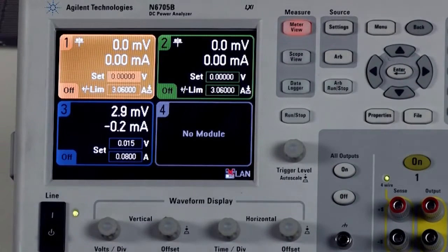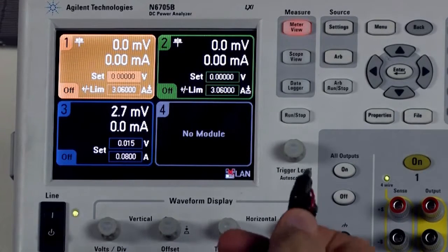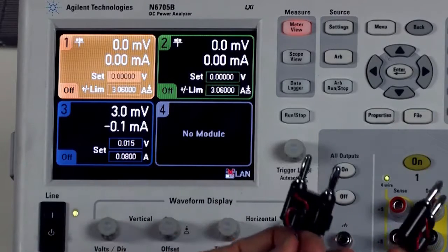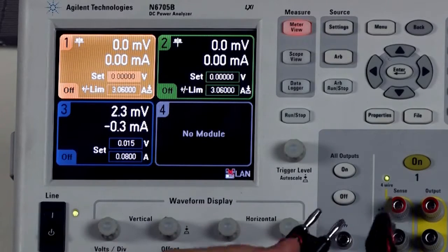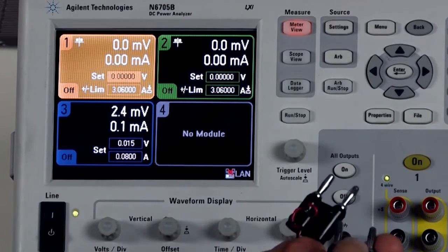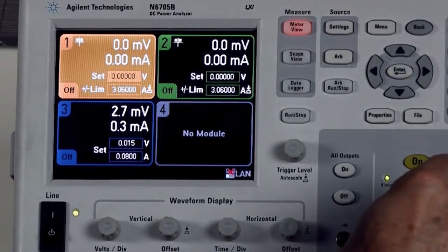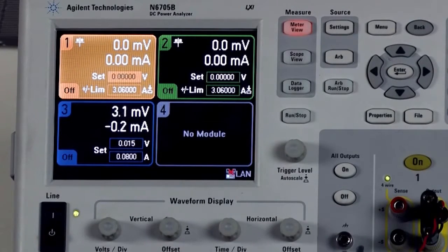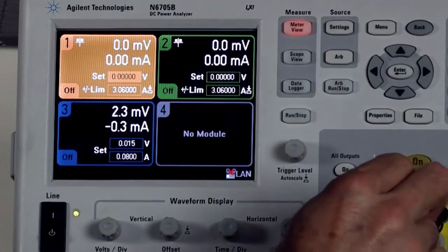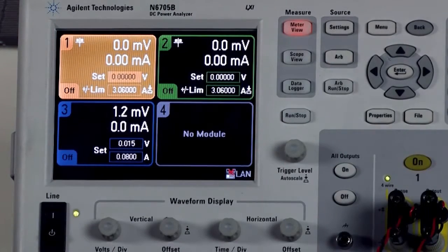Secondly, we want to connect our pulse oximeter. You can see that we have 2 twisted pairs here. One is for the output, and we want to make sure that the red wire is on top. The other one is for the sense, because we do want to use remote sensing and sense down where we're connected to our pulse oximeter. We're basically replacing the batteries in this device.